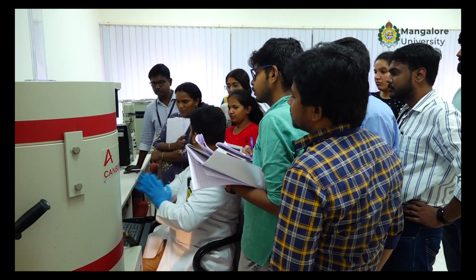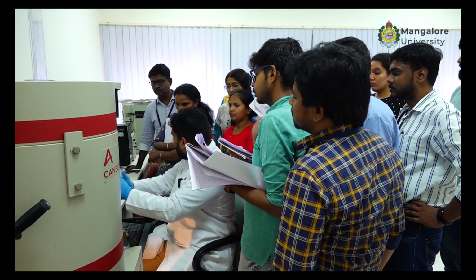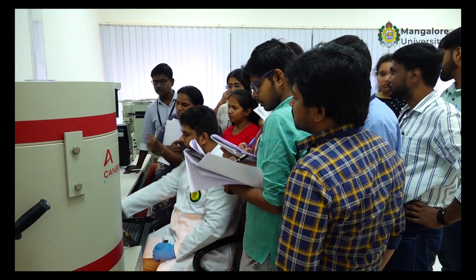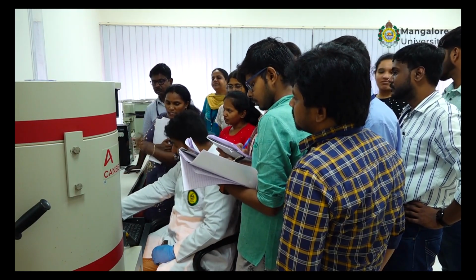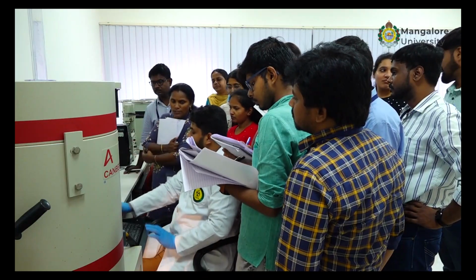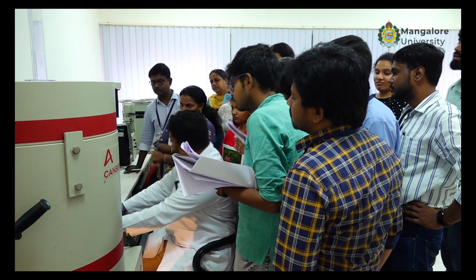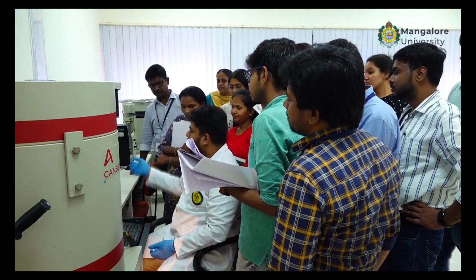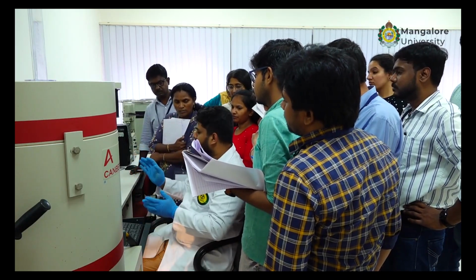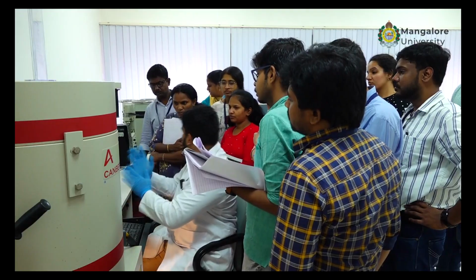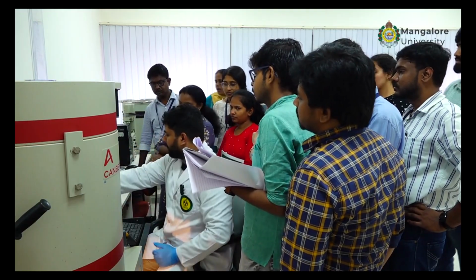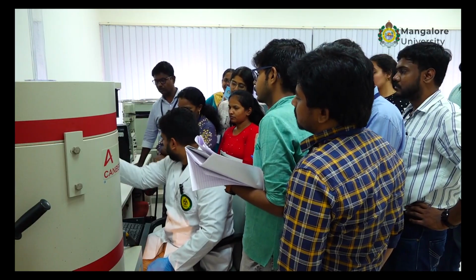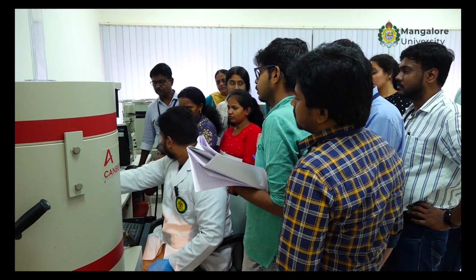So I don't have to worry whether the identification of the radionuclide is proper or not. Correct? So actually, you are placing this point source to identify whether the calibration is correct. If this is not right, what I will do is play with the amplifier. I will change the amplifier settings, the gain settings, in order to make this fit the curve. Suppose it is over here. I have super fine gain or fine gain, that coarse gain, to shift this to this location.